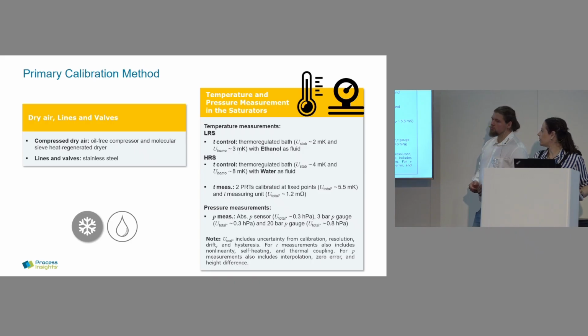To achieve this level of uncertainty, I just put there the numbers that we have. So the stability of the bath and homogeneity of the bath, 2 and 3 millikelvin for the low range; for the high range, we have 4 and 8. How can we achieve this? We use PRTs calibrated in fixed points with 5.5 millikelvin, the temperature measuring unit with 1.2 milliohm, and for the pressure we have 0.3 hectopascal, and for the 20 bar 0.8. Of course, when I'm talking about this U total, it includes the drift, resolution, hysteresis, all these sources that we need to add. So it's already included in this total.